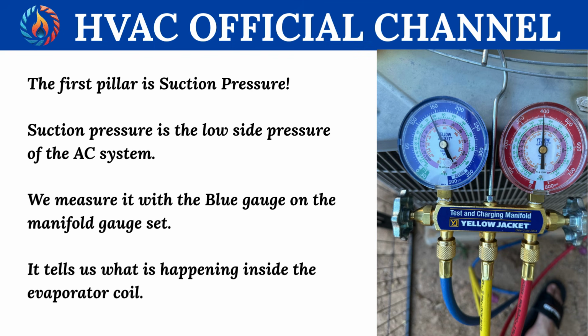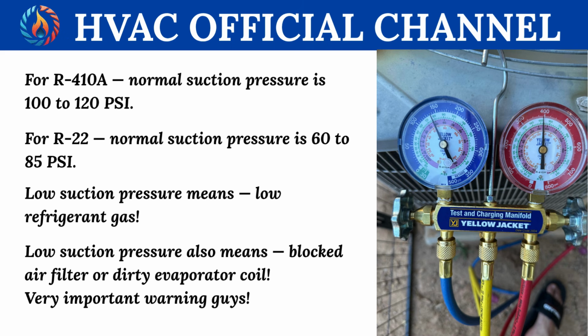The first pillar is suction pressure. Suction pressure is the low side pressure of the AC system. We measure it with the blue gauge on the manifold gauge set. It tells us what is happening inside the evaporator coil. For R410A, normal suction pressure is 100 to 120 psi. For R22, normal suction pressure is 60 to 85 psi.